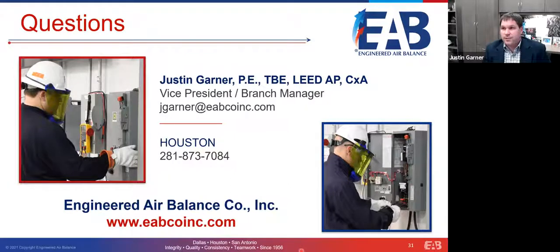Using that formula that I showed. It's not going to be actual, like if you put a power analyzer on it. If you need the exact number, I would encourage you to use an actual power analyzer or power meter. But if you want to estimate it, and it's a very good estimation, if you go through the steps that we outlined and follow that formula, you can do everything. Obviously, you're going to need a little bit of extra data, typically those no load figures for the motor. If you follow those steps, you can get there.